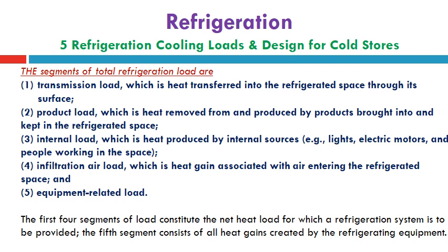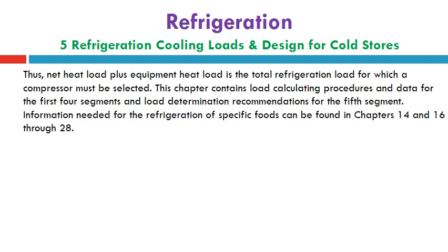The first 4 segments of load constitute the net heat loads for which the refrigeration system is to be provided. The fifth segment consists of heat gains created by refrigeration equipment. Thus, net heat load plus equipment heat load is the total refrigeration load for which a compressor must be selected. This chapter contains the load calculating procedures and data for the first four segments and the load determination recommendation for the fifth segment. Information needed for the refrigeration for specific foods can be found in chapters 14 and 16 through 28.